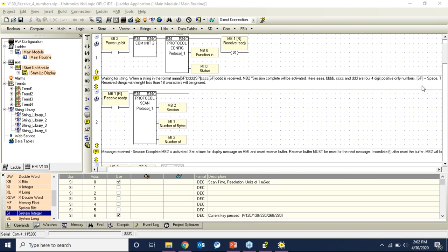In Modbus protocol, can you use both RTU and TCP, or are you limited to one or the other? If you have both a serial port and an Ethernet port, they can act independent of one another — that's your other means of getting around half-duplex. How can I send email through PLC? Take a look at the email example we went over; the most important thing is the email server being non-encrypted. You cannot use a Gmail account, for example. On the Unistream, you can use SSL encrypted accounts. For Gmail specifically, you also have to go into your account settings and enable less secure applications.